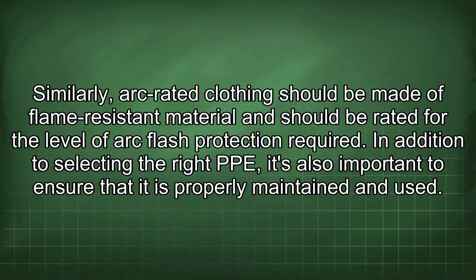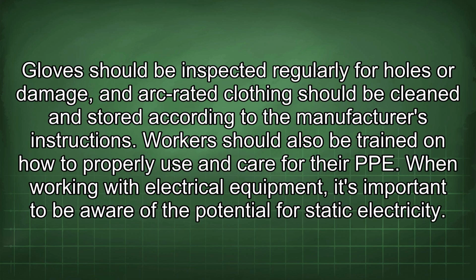Similarly, arc-rated clothing should be made of flame-resistant material and should be rated for the level of arc flash protection required. In addition to selecting the right PPE, it's also important to ensure that it is properly maintained and used. Gloves should be inspected regularly for holes or damage, and arc-rated clothing should be cleaned and stored according to the manufacturer's instructions. Workers should also be trained on how to properly use and care for their PPE.